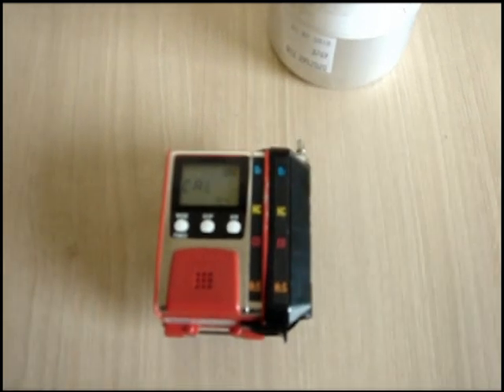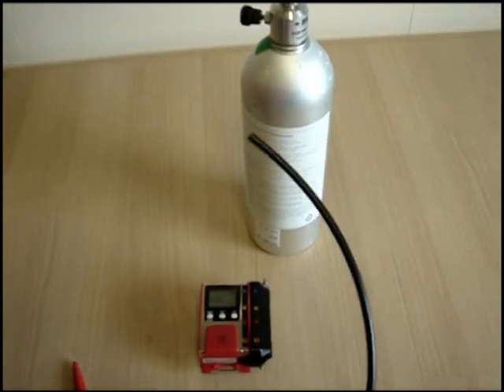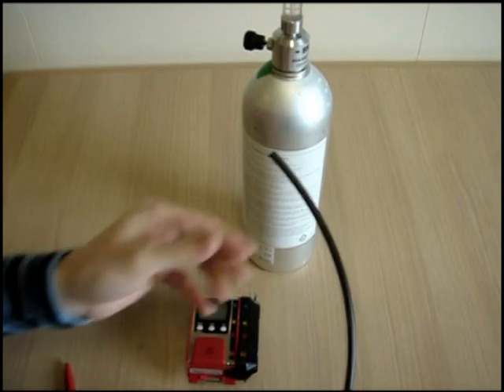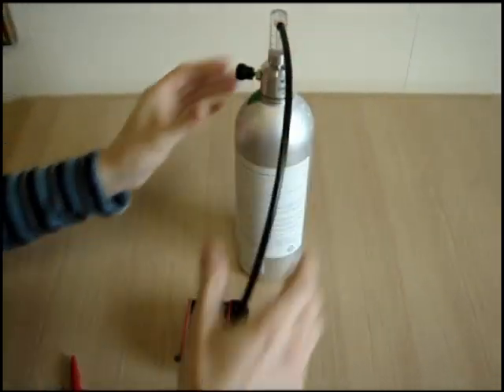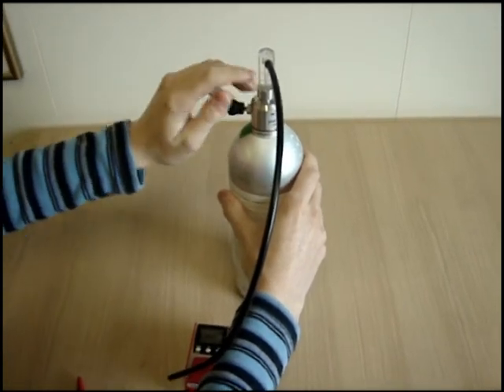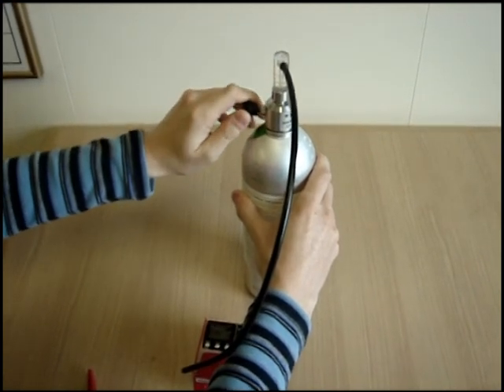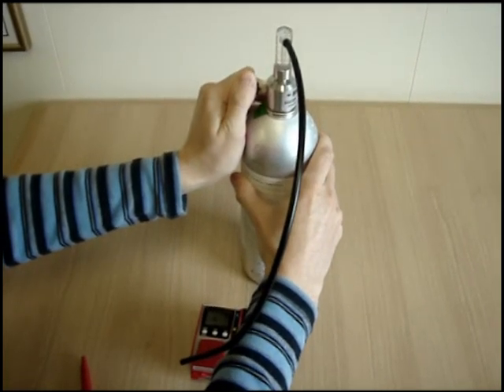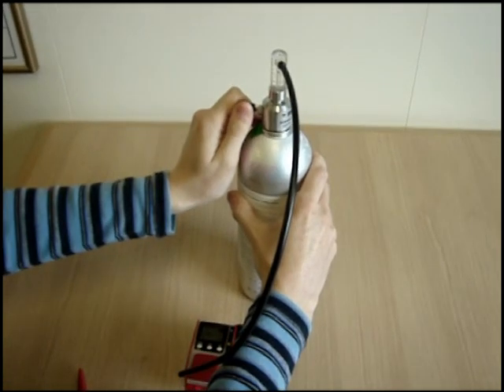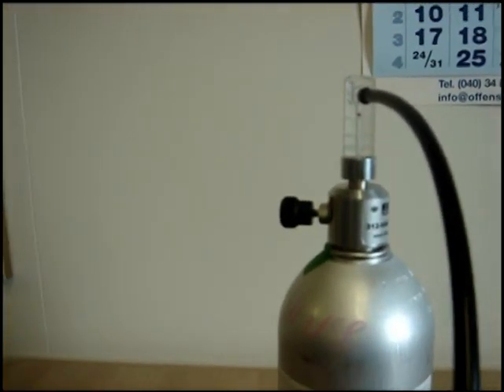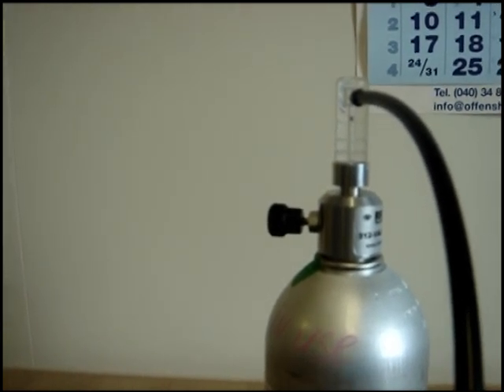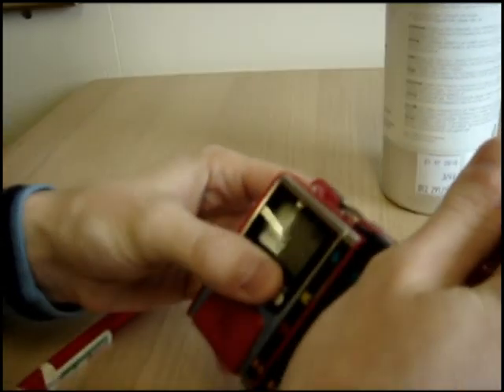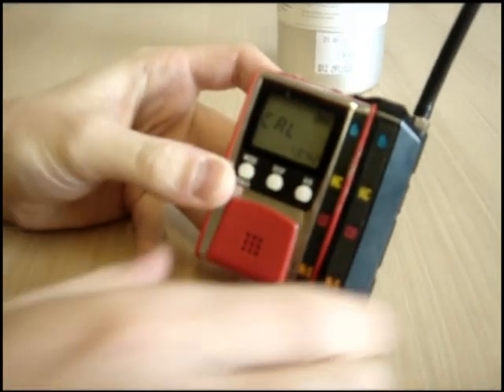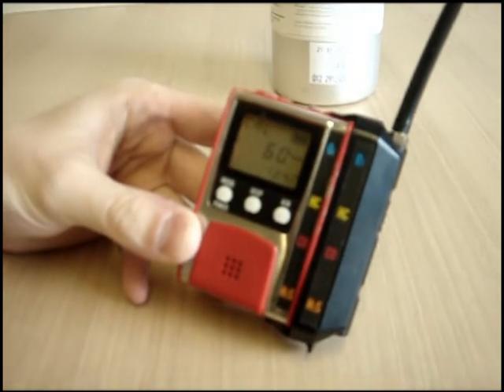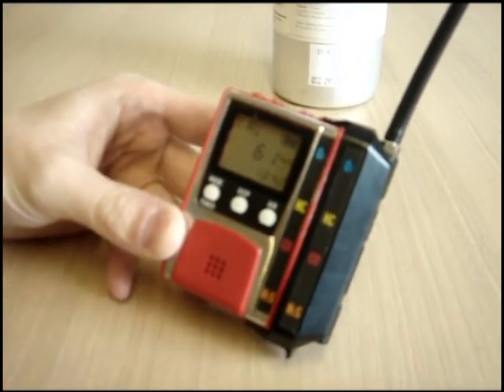Before this, we will need to connect the portable hose to the bottle, open the span gas and make the gas flow through the device. We open the flow meter to make it approximately 0.5 liters per minute, the consumption of the span gas. You can see the ball is rising, that means that the gas is passing. Now we connect the portable hose to the device and we push the power button to enter the calibration. Now you have the readings of the calibration and the gas.